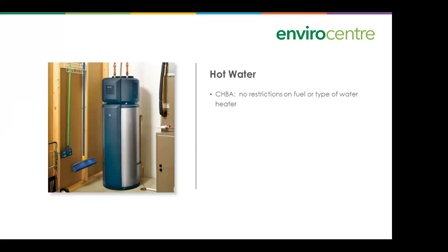Hot water. There's no restriction on the fuel or type of water heater. However, when modeling net zero, heat pump water heaters are pretty much necessary. It's very difficult to get into net zero territory with our high base loads without that kind of efficiency in your water heater. So they should be coupled with the longest possible drain water heat recovery unit, installed on a vertical stack. The longer they are, the more efficient they are, and it should be fairly close to your tank.